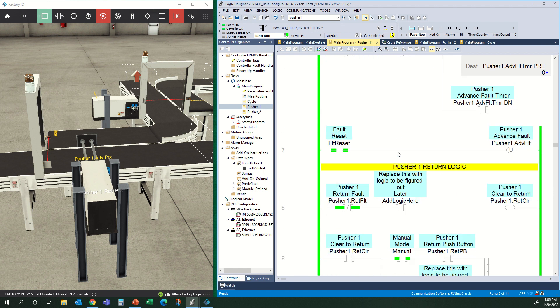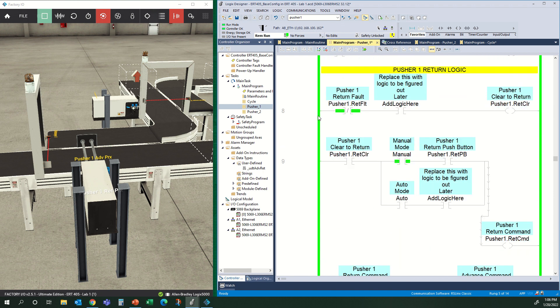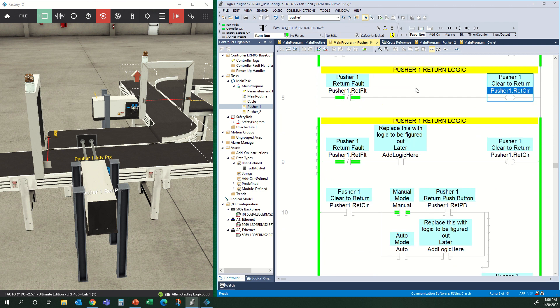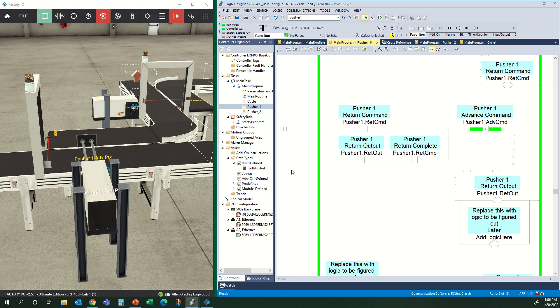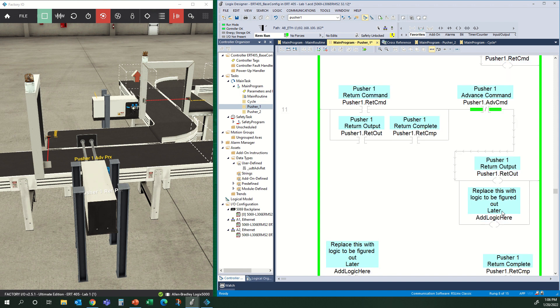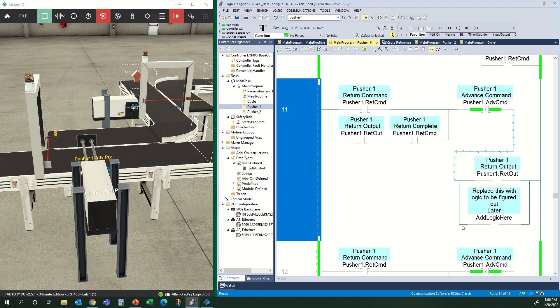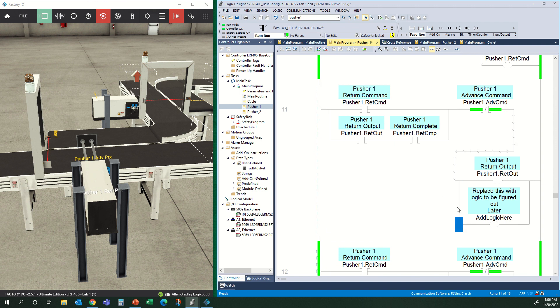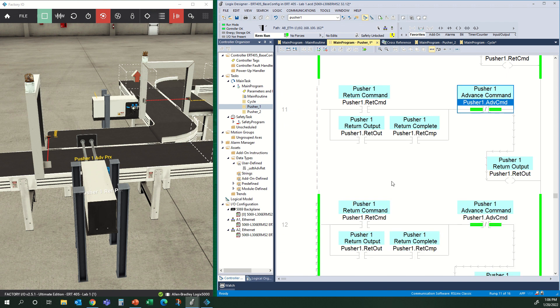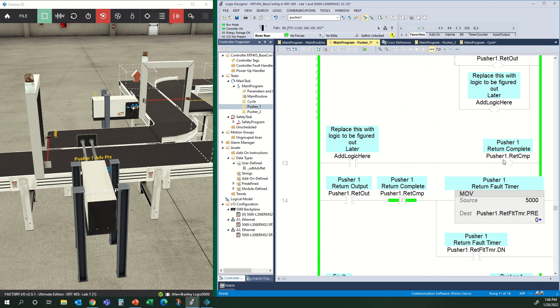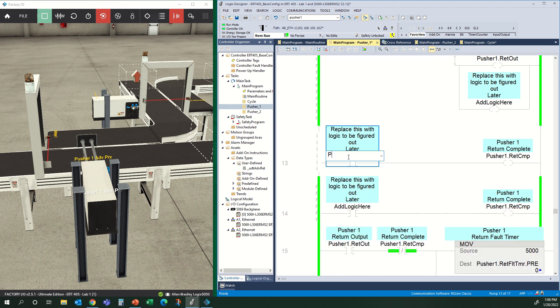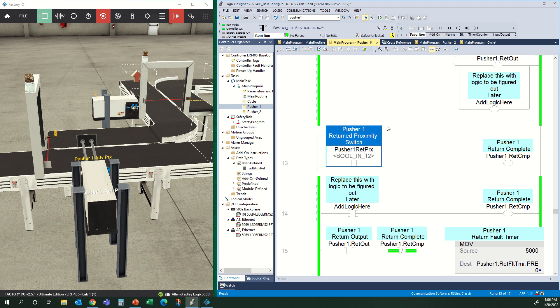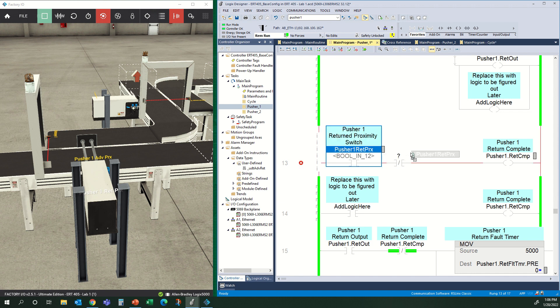Let's go through the return as well. What makes this clear to return? There are no obstructions there, so we'll get rid of that placeholder. Is there a physical output that makes us return? There actually isn't — this is a single solenoid device, there is no output for return, so we can just remove that. What defines us as returned? Pusher 1 Return Prox is on, and not the Pusher 1 Advanced Prox. This is the basic process we will do when we create these motions — go back and figure out what needs to go in place of all the Add Logic Here spots.